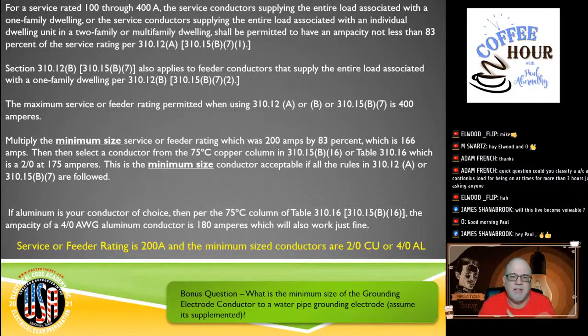So in this case right now, we know the rating is 200 amperes and we're doing a service. So we're going to be applying 310.12A for our application. So multiply the minimum size service or feeder rating, which in our case is 200 amps, by 83%, which is 166 amps. So let me do this.